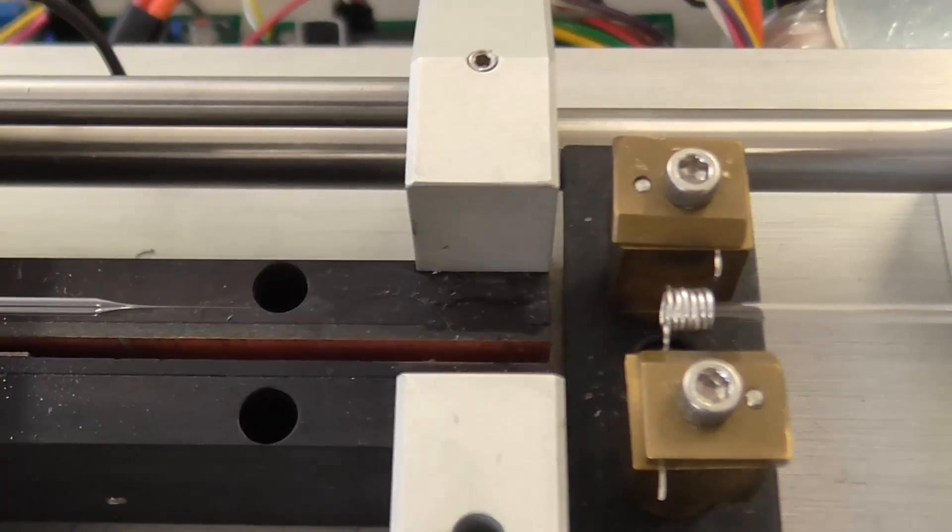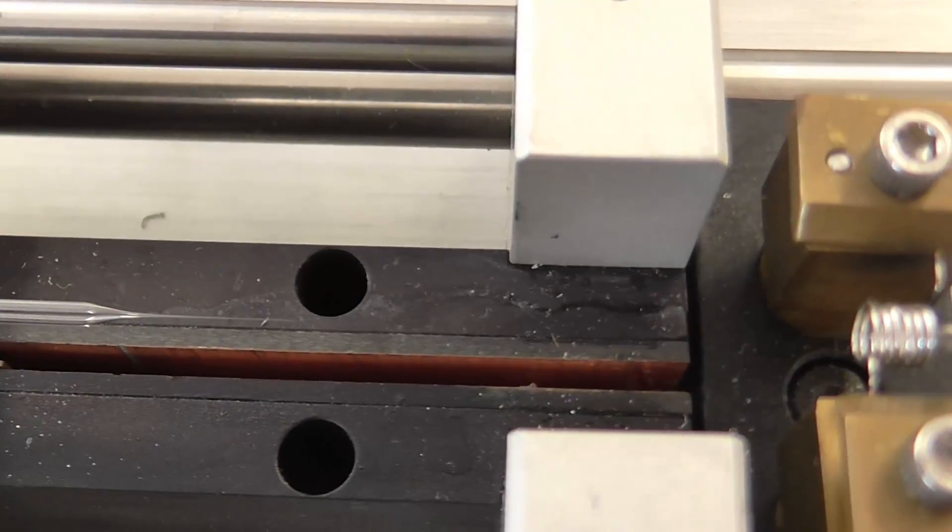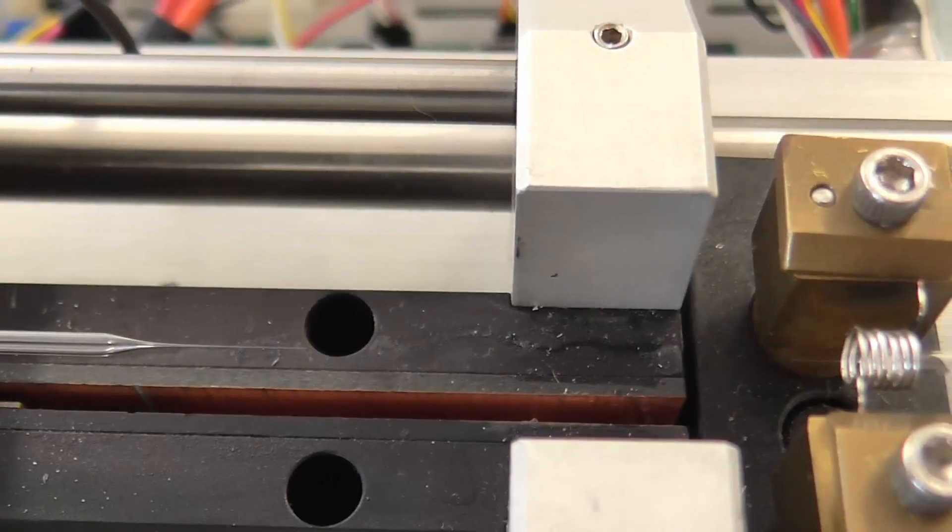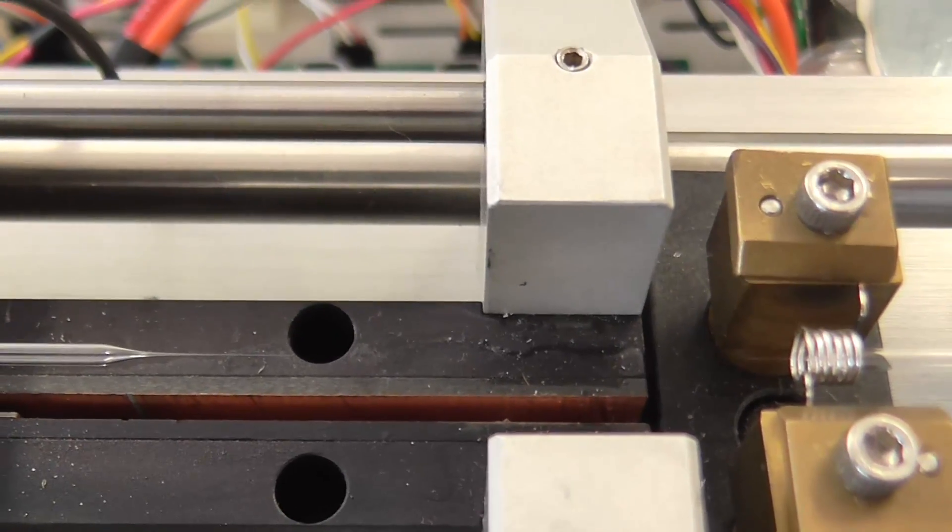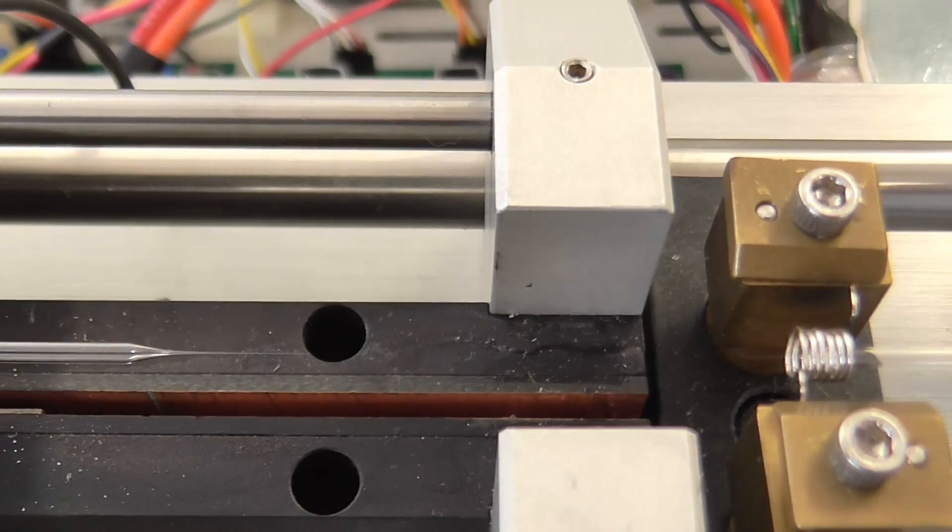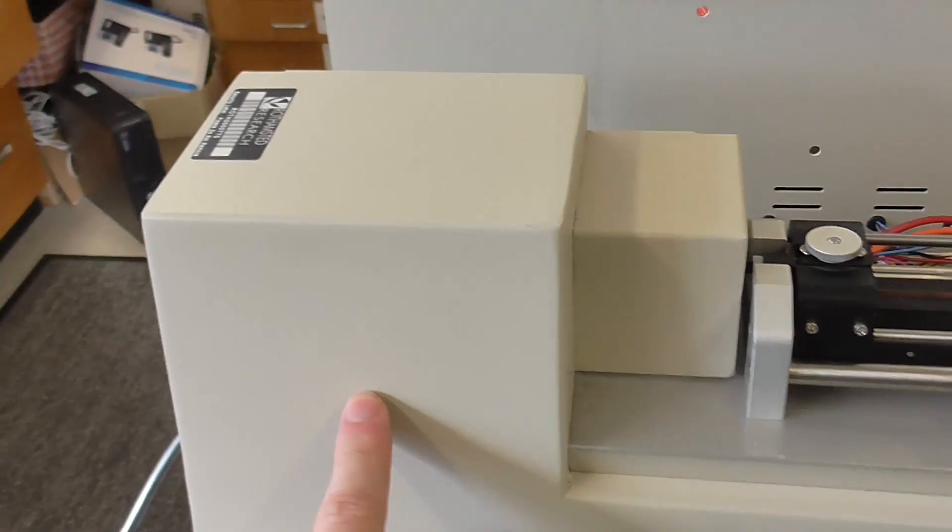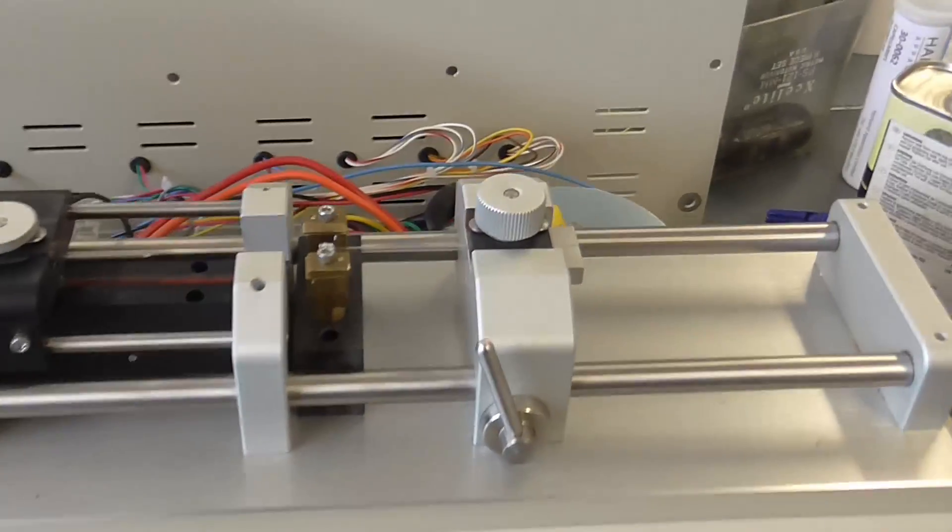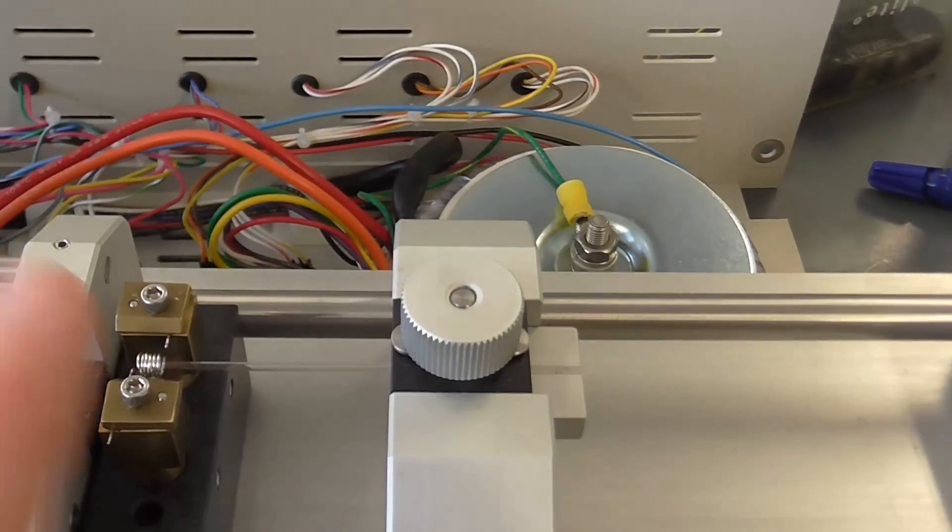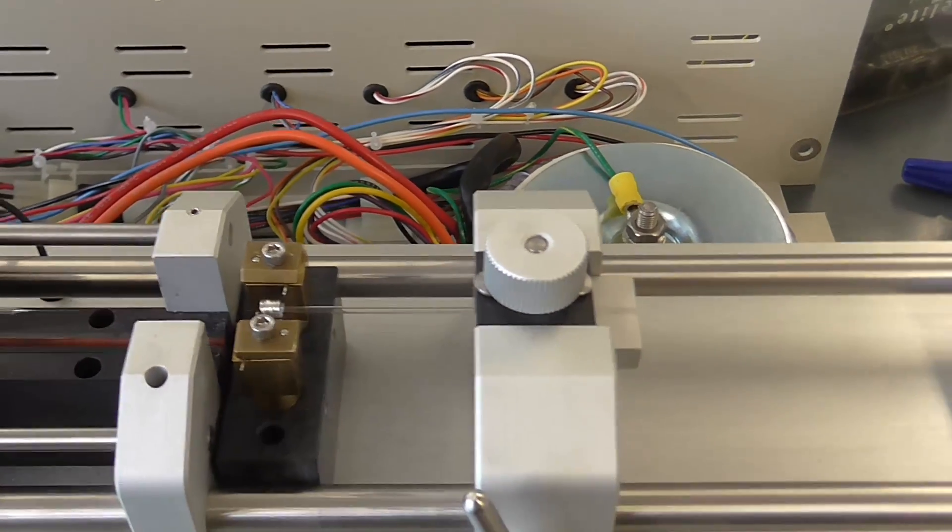And if I come in really tight, you can see the very fine glass pipette that's been pulled. By altering the current in the pulse solenoid and the heat levels and the time it's been soaking the tube, there are a series of programs so you can set the shape and fineness of the pipette you create.